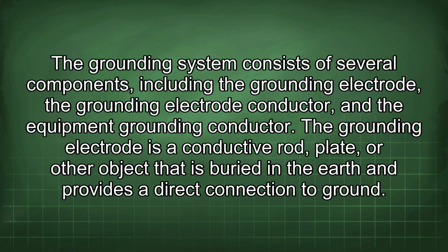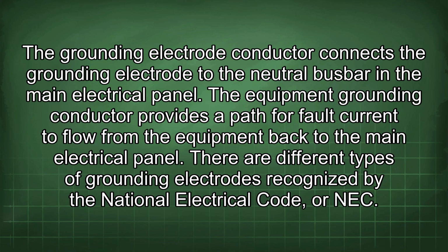The grounding system consists of several components, including the grounding electrode, the grounding electrode conductor, and the equipment grounding conductor. The grounding electrode is a conductive rod, plate, or other object that is buried in the earth and provides a direct connection to ground. The grounding electrode conductor connects the grounding electrode to the neutral busbar in the main electrical panel. The equipment grounding conductor provides a path for fault current to flow from the equipment back to the main electrical panel. There are different types of grounding electrodes recognized by the National Electrical Code, or NEC.